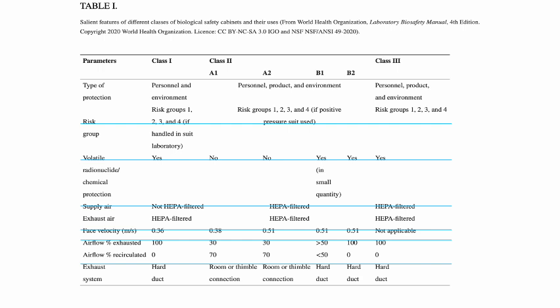When we say face velocity class, it is usually applicable only for biosafety cabinets that have an open front window, an open front type biosafety cabinet. That includes Class 1 and Class 2. Face velocity is how fast, or how much, air is supplied by the blower. Next is the percentage of the air that is exhausted and also recirculated in the biosafety cabinet. And lastly is the exhaust system.